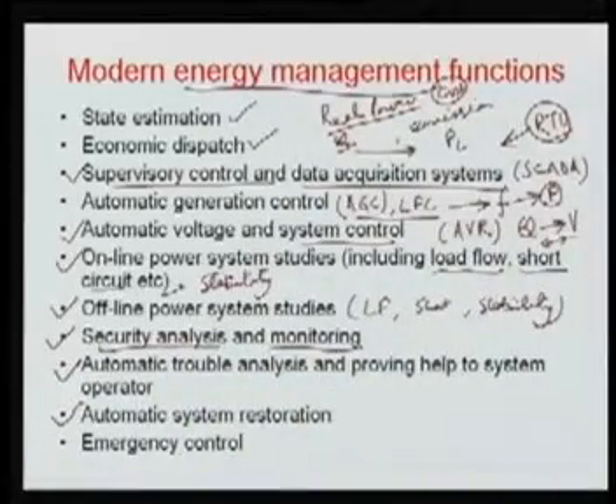This is the main aim of the system operators, that the system must be restored in as minimum time as possible. For that, we require automatic system restoration procedures. Because if it is manual, it will require a large time, and during that interval you are not supplying electricity to your customers. That is a huge loss of revenue and also a huge loss of customers. So automatic system restoration procedures are applied, and again they vary from system to system. It is not unique, but there are some guidelines.